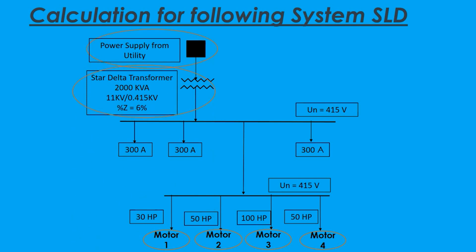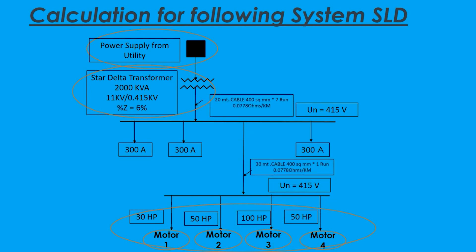This system consists of a source of 11 kilovolts and a transformer of 11 kV by 0.415 kV, with four motors connected as load operating at 415 volts. For power transmission, seven runs of 20 metre 400 square millimetre cable and one run of 30 metre 400 square millimetre cable are used.